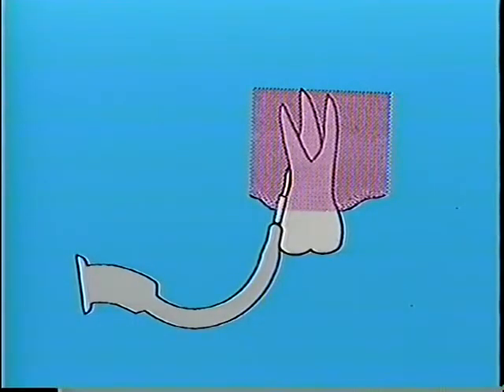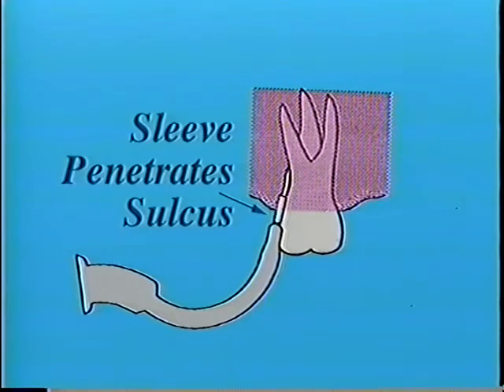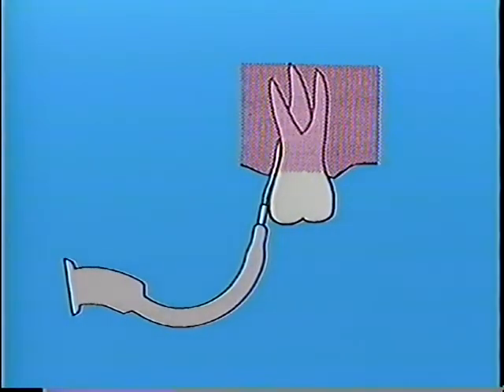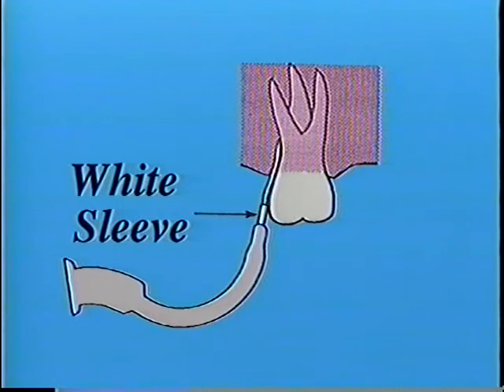Initially, you may get shallow readings in pockets that you know are actually much deeper. That's usually a sign that you're allowing the white sleeve to penetrate into the gingival pocket, thus creating an artificially shallow reading. On the other hand, if you're getting deep pocket readings that you know are relatively shallow, you may be pressing the foot pedal before the white sleeve has reached the gingival crest.